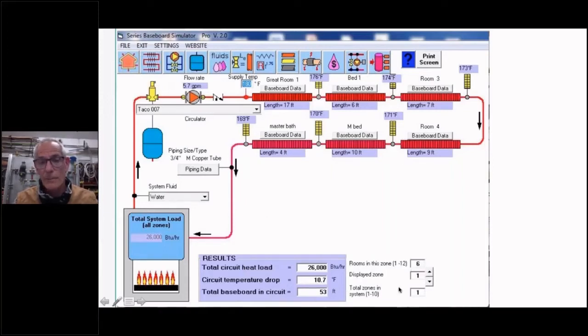I can just go down here and put another zone in, and it would split off another zone, and I could do maybe the upstairs or the basement as a separate zone. And the same thing, I could toggle on different circulators, different operating conditions, and just see what the result is, how much heat I'm going to move, what my temperature drop is through that circuit, all that stuff. So if you're doing this type of design work, this is a pretty handy little calculator to give all the information to you.